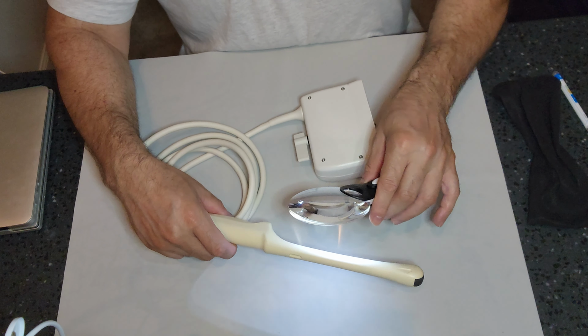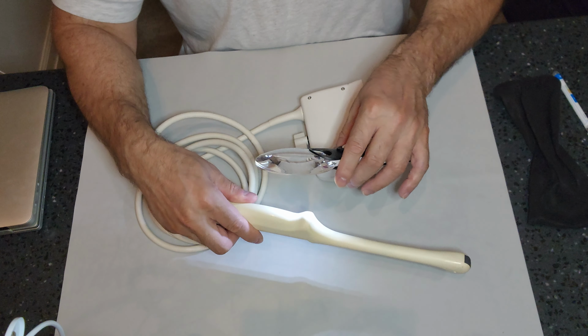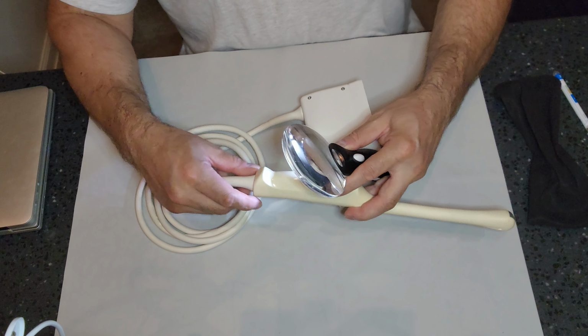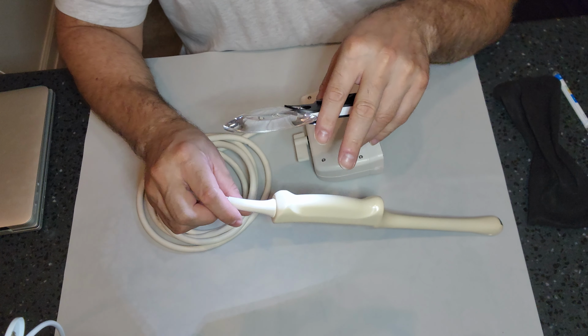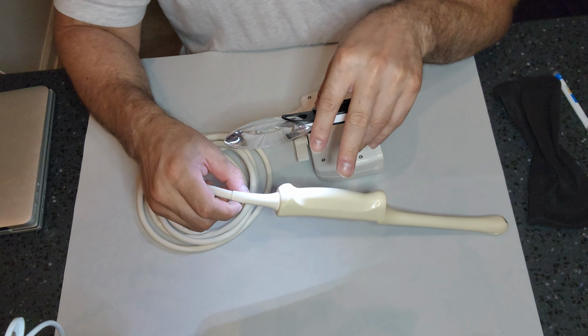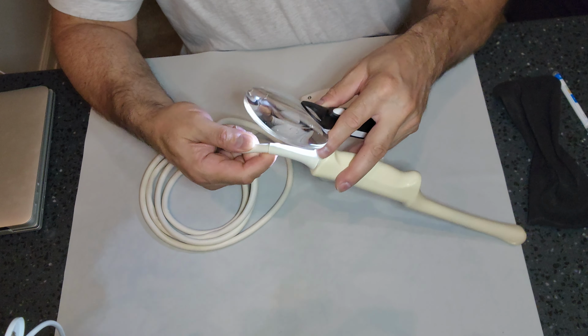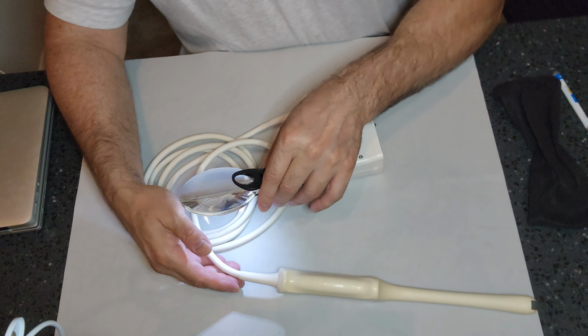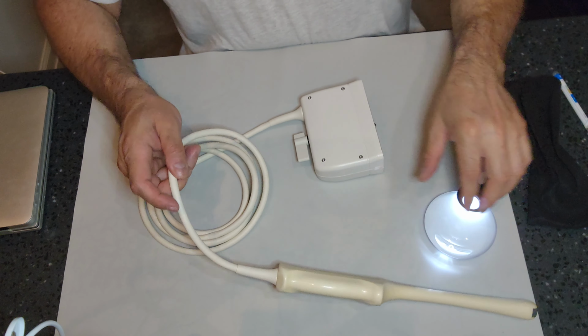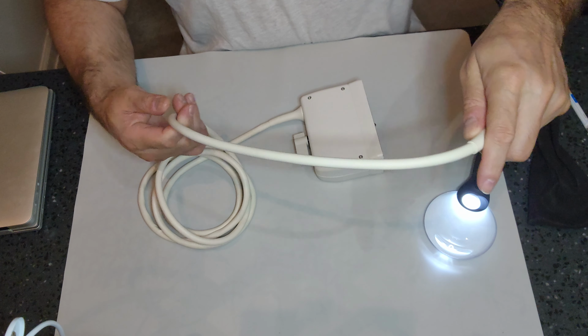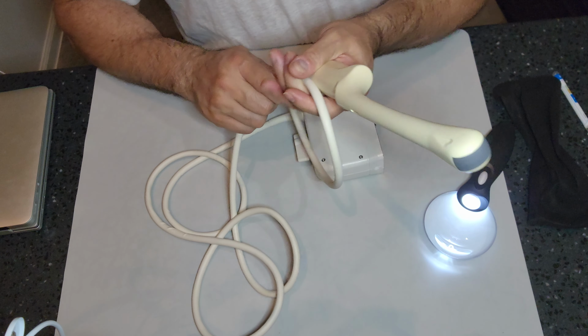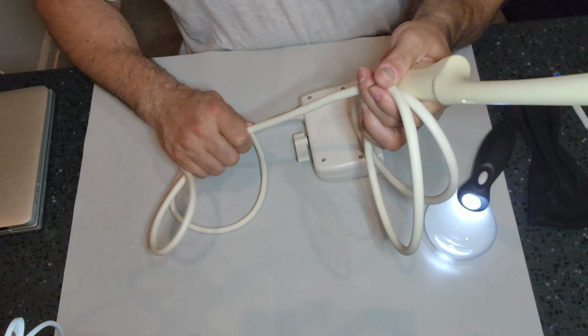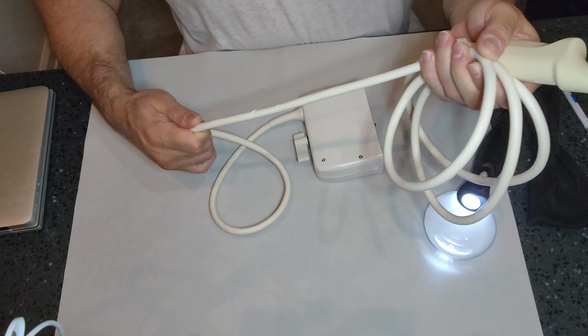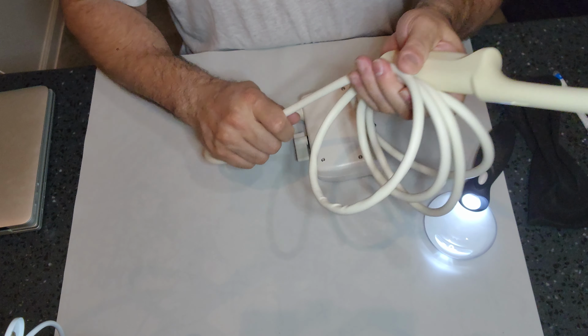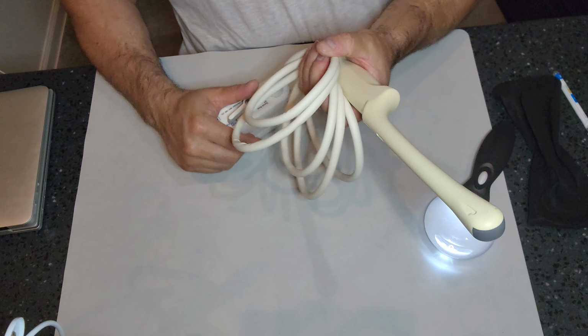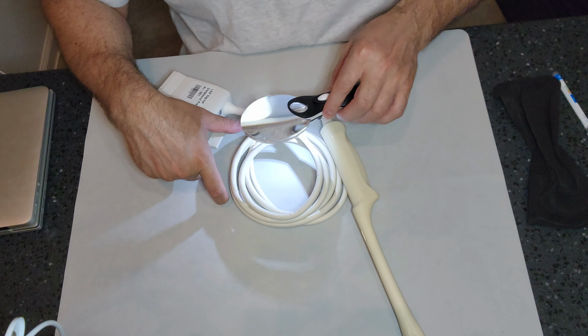We want to inspect the whole probe body for any cracks or breaks, any discoloration, any soil, right? We want to go ahead and check the connector, the neck where the body connects to the cable. Make sure that there's no cracks or any moisture seeping out of there. And then we want to inspect the cord for any cracks. Again, your first line is to run your hand down there, right? Hold your probe in your hand and run the cord through your hands. Feel for any nicks or cracks or cuts in that cord. Again, get your lighted magnification out and do the same process with your cord.